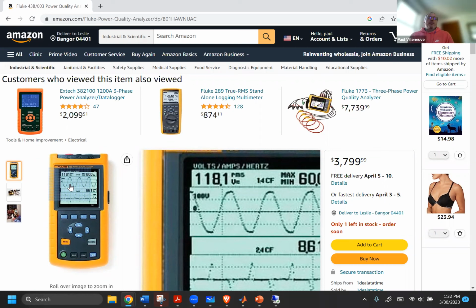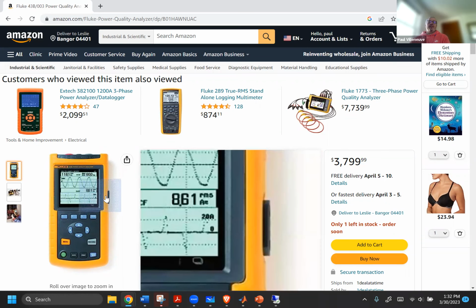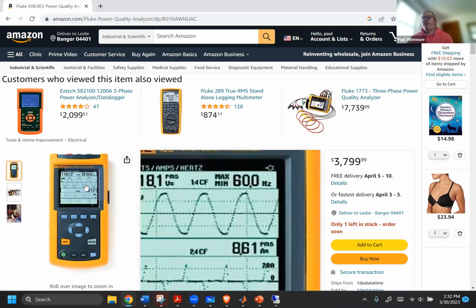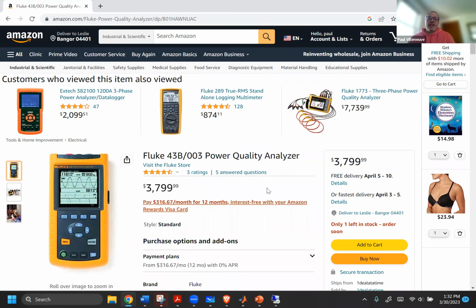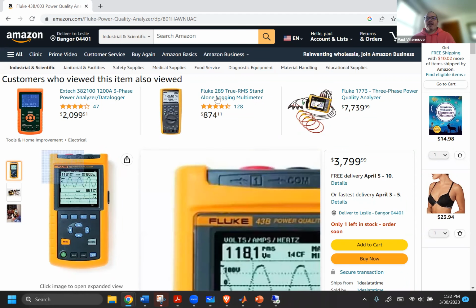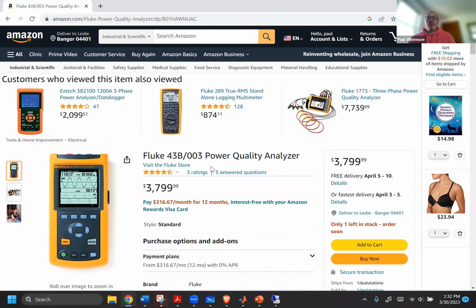Well, so that's just it. The newer devices can actually calculate that. But what they used to do, that wasn't always available. So that's why a lot of the work we've done is just measure power. And keep in mind, some of these devices, if you're measuring a 1,000 horsepower motor or a 50 MVA transformer, you can't buy this, this is kind of expensive, $3,000, but you will get cheaper pieces of equipment that can actually measure power. So yeah, you can buy this on Amazon, and this is power quality. If I just want a basic power meter.